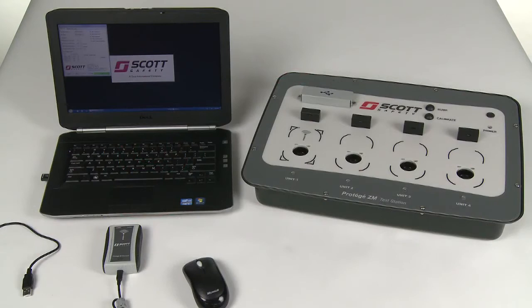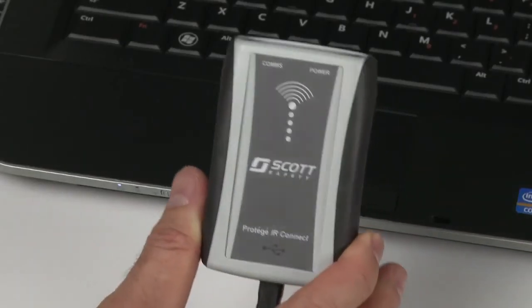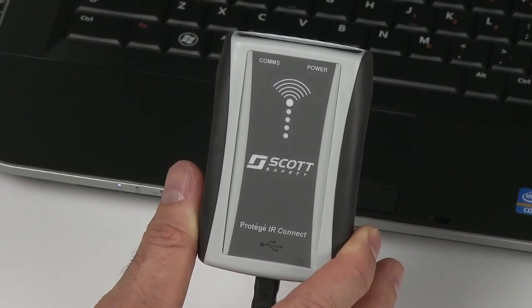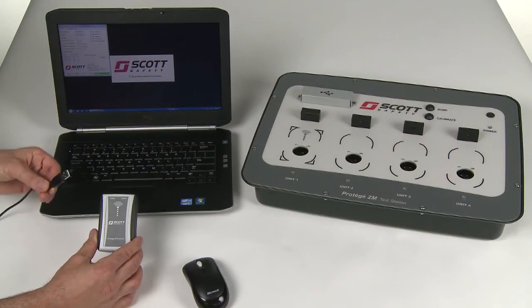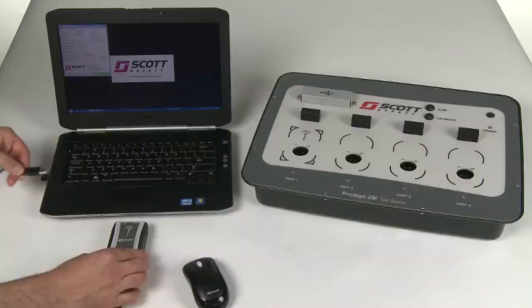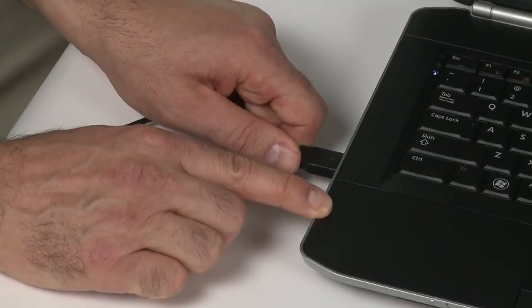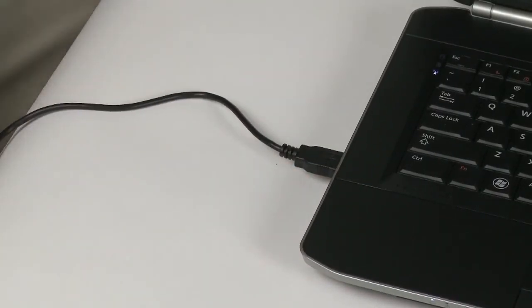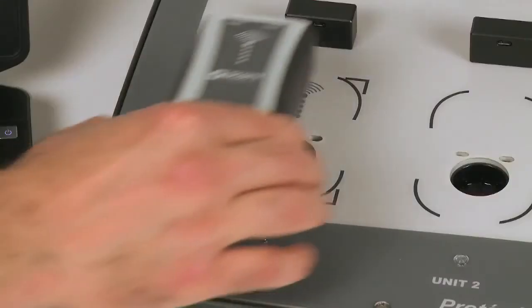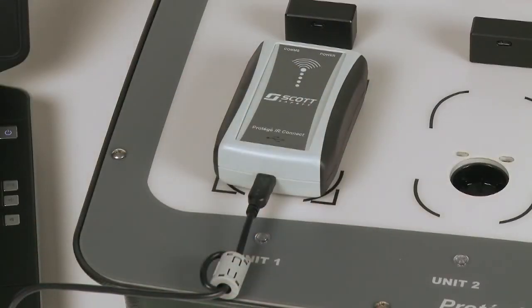When monitors are tested using the test station, they are also programmed with any custom settings stored on the test station. You can use the IR Connect accessory to change the custom settings stored on the test station. To use the IR Connect to program the test station, plug the IR Connect USB cable into the USB connector on your computer. Place the IR Connect in bay number 1 on the test station. The IR Connect can only be used in bay 1 and will not work in bays 2 through 4.